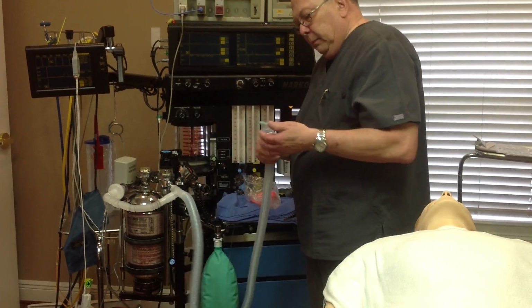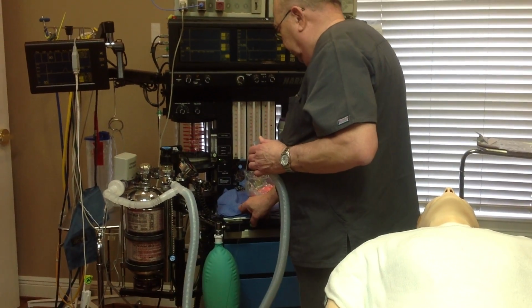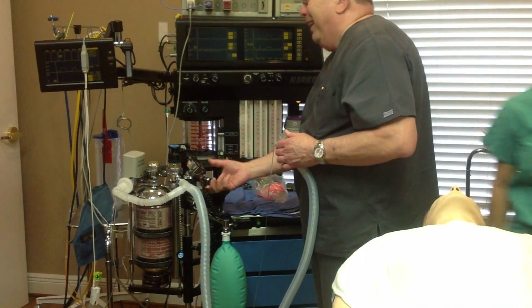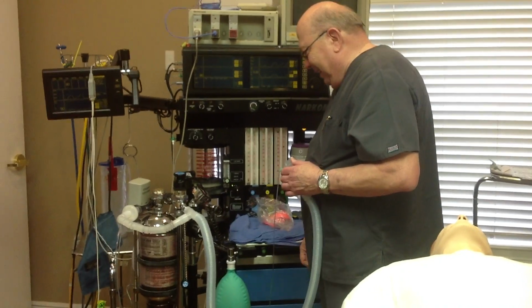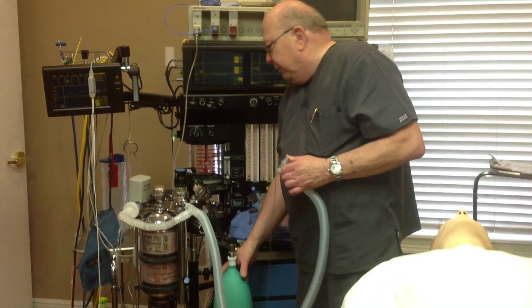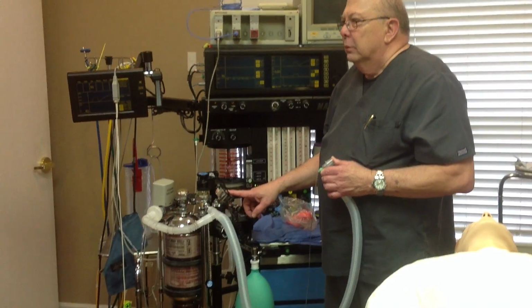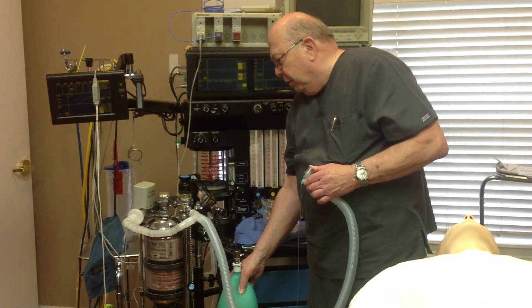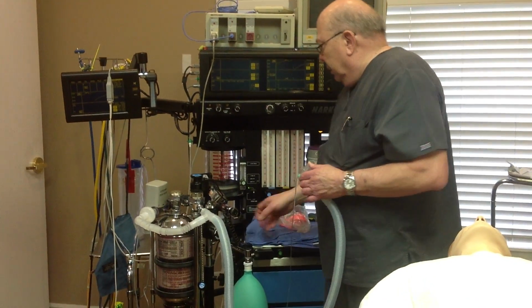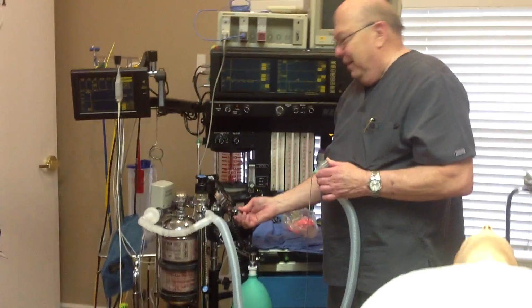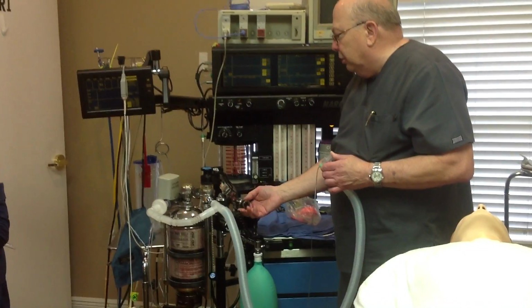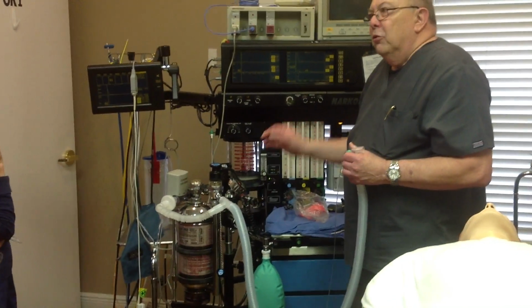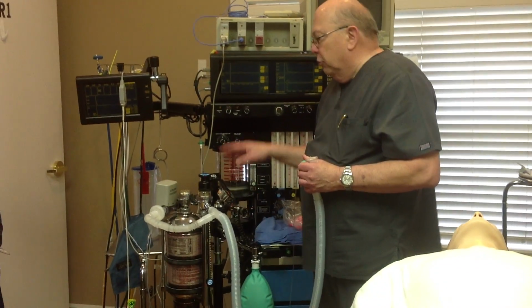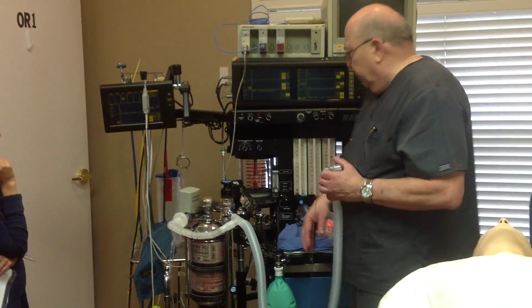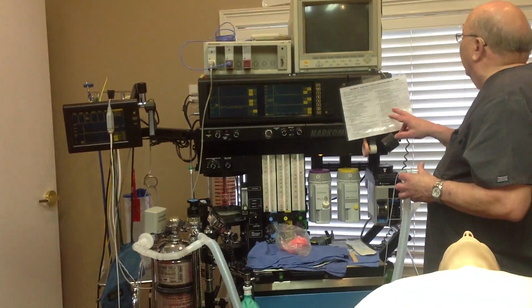What's our problem today? Close your APL valve. Yeah. Close your APL valve, and you're going to make it go up to 30 centimeters of pressure. Okay? And I can push here if I had to. And now I saw it's giving me high pressure. So now I'm going to open my APL valve again and release it, and the pressure should come down, and the bag should collapse. So we checked that the APL valve is fully functional, and there's no leak in our breathing system. Now, my next step is number 12.